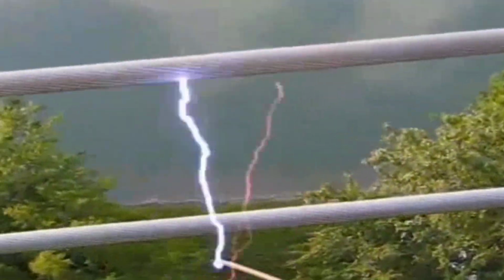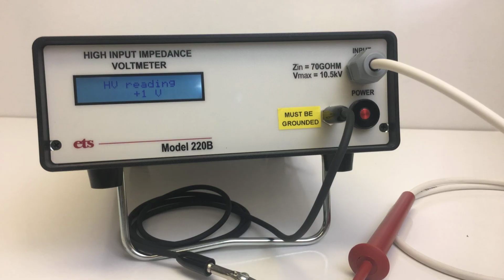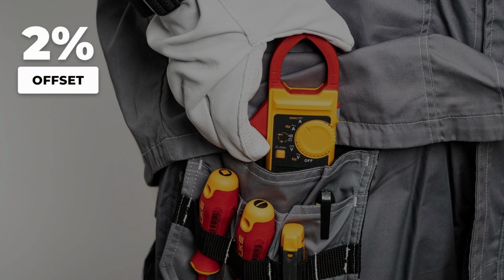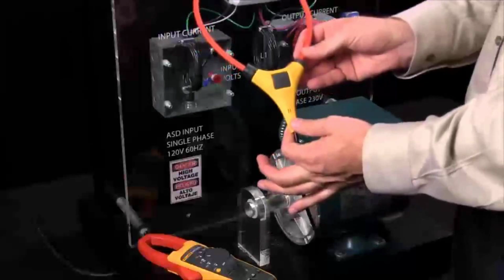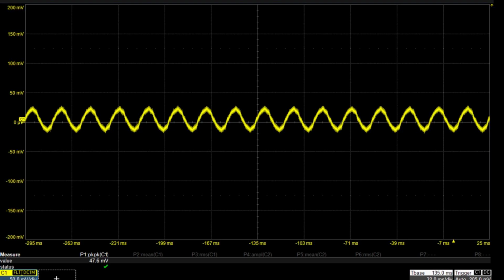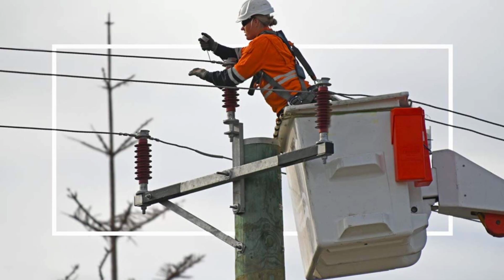The bonding process is exact. A high-impedance voltmeter checks that the suit's bonding point matches the line to ground voltage within 2%. The clamp is applied, and a current probe measures the brief surge, typically 10 to 30 amps, until the suit equalizes. Only then does work begin.